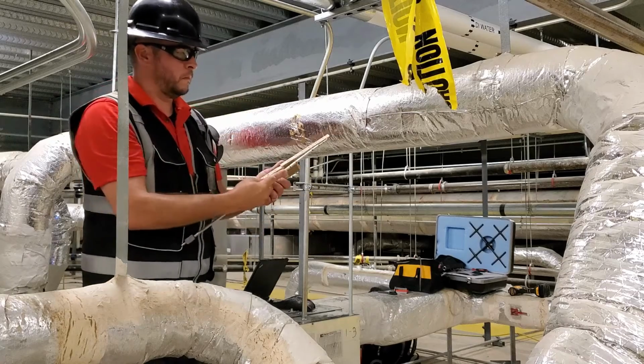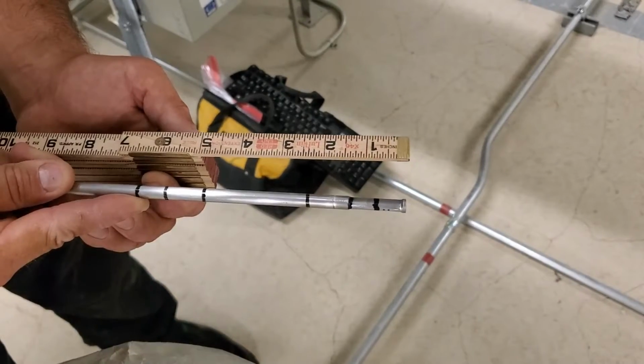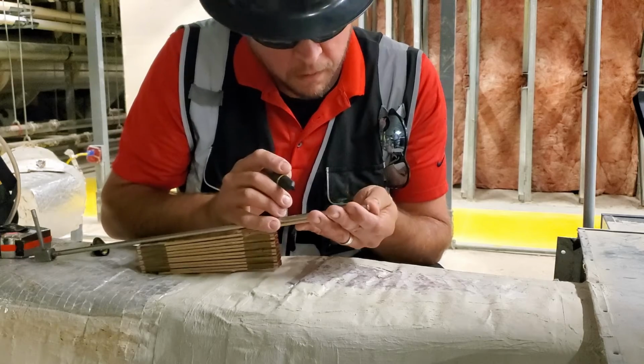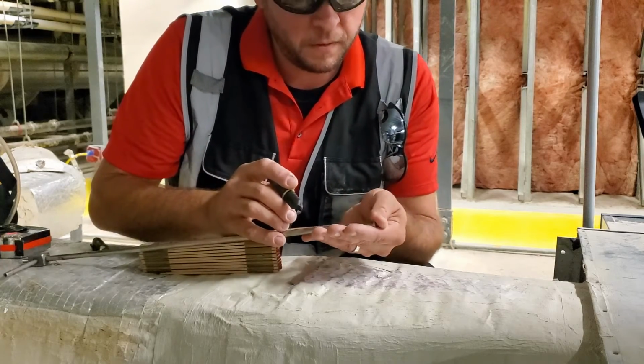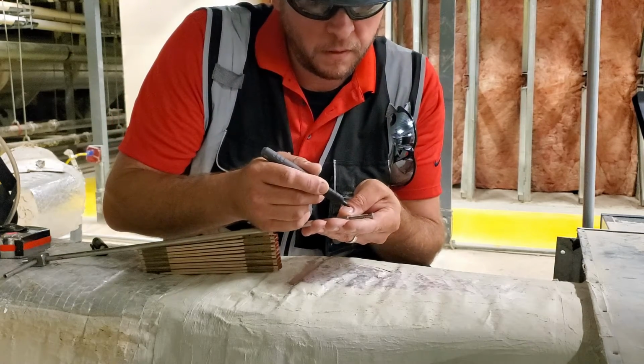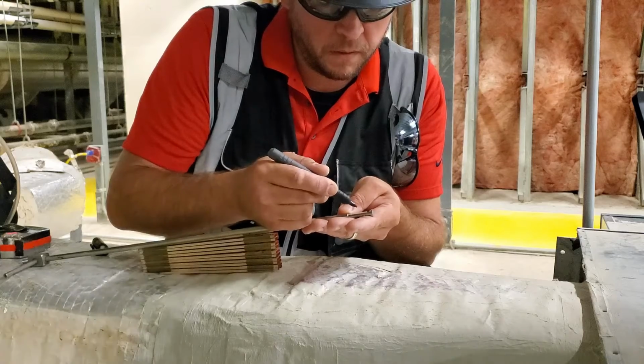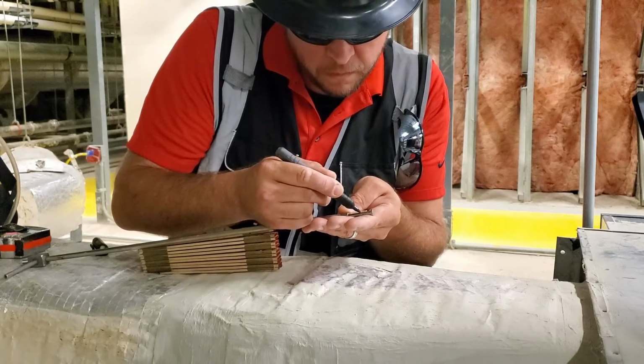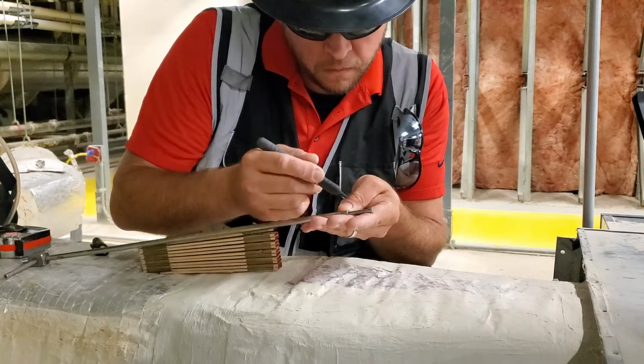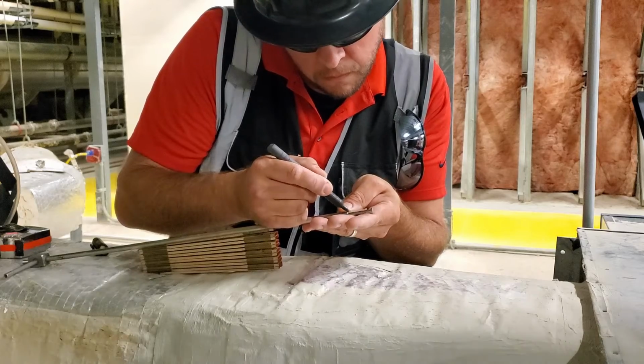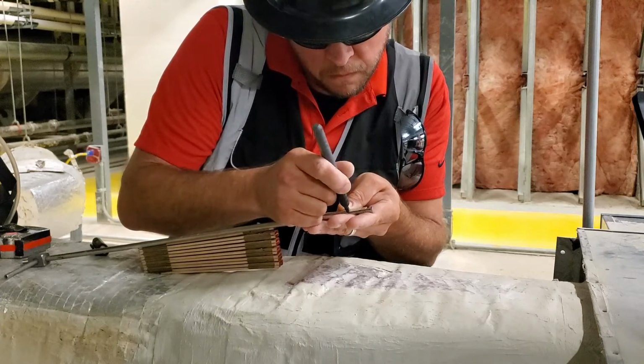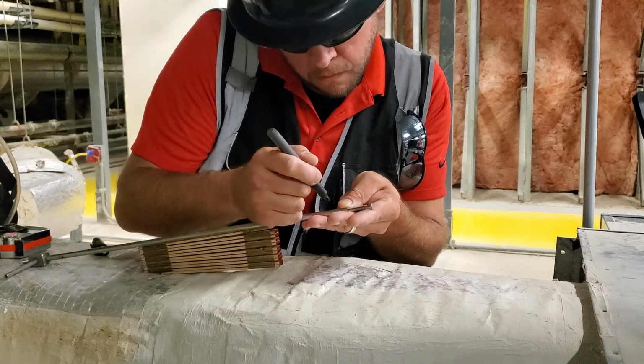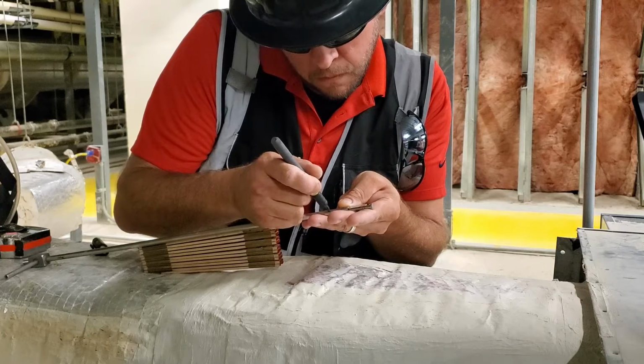And in this case, we're looking at a dual duct terminal unit with a 6-inch inlet, as you can see. And once you've determined how you're going to calibrate the unit, obviously you don't have to do a traverse. You can calibrate it using a flow hood. But in this case, since we're in an interstitial space, we've chosen to do a traverse with the airfoil.